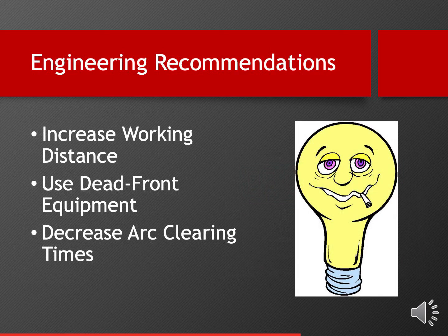From the engineering recommendation side, there's really 3 things that we can do primarily to make our situation better for our workers. The first one is to increase the working distance on the system that we're working at. So for example, anything you can do to add some distance between your chest and the arcing terminals of the equipment, you could do it. And we'll talk about how to do that here in a little bit.